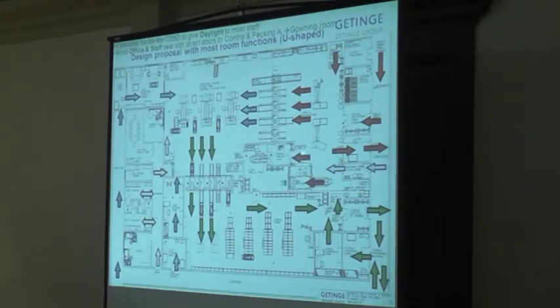And the soil trolleys go through a cart washer, clean trolley route. The trolley goes down to the sterile store and is packed with items and goes out. And we have a backup function with the manual trolley wash, in case we need to service this, so we don't stop the entire production. And again, U-shaped flow. This is positioned here, so we take down the trolleys here, the clean basket containers in that direction. And here we have an airlock between the packing area and the sterile store.